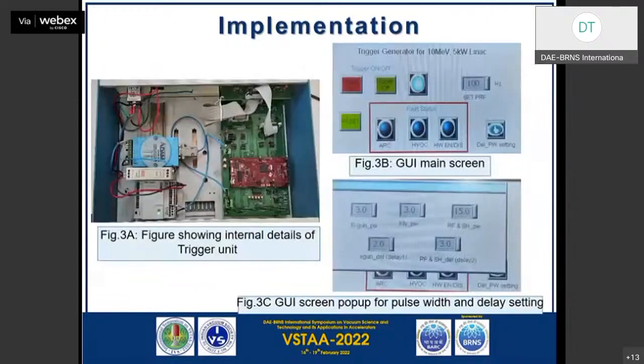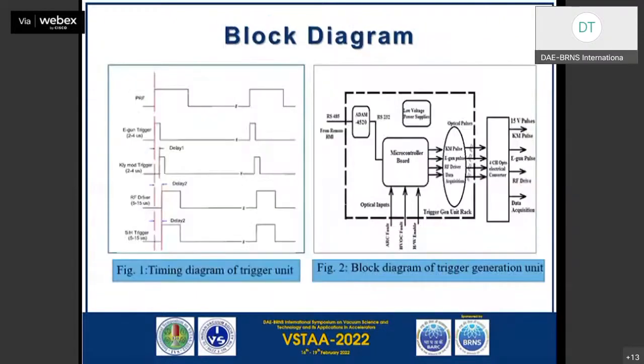In figure 2, we can see the block diagram of the trigger generator unit. In this, we have one microprocessor card which uses two 32-bit CPUs, and this trigger unit accepts fast interlocks in the form of optical inputs, and it generates 4 synchronized triggers in the form of optical. To connect these triggers in the field, we have one optical to electrical conversion board, which is installed in the field. And for RTU Modbus communication, we have an ADAM module. By using that, this unit can be connected to the remote HMI.